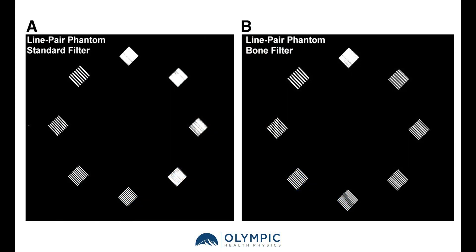In the example we have here, we're looking at the resolution pattern in a CT phantom — looking at how well the system can display detail in the image. In the image on the left, where we're using a standard filter, we can actually see down to the seven line pair target.